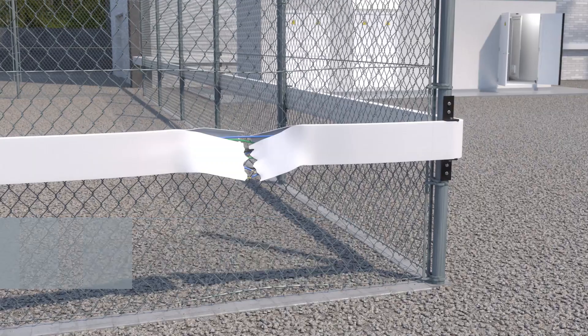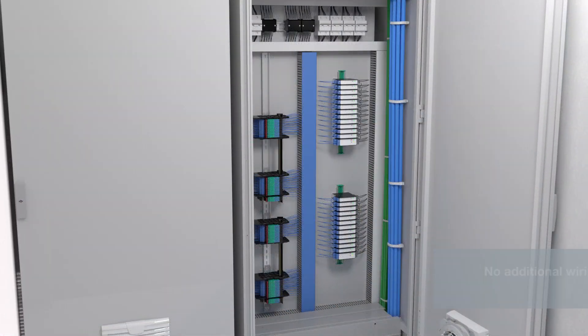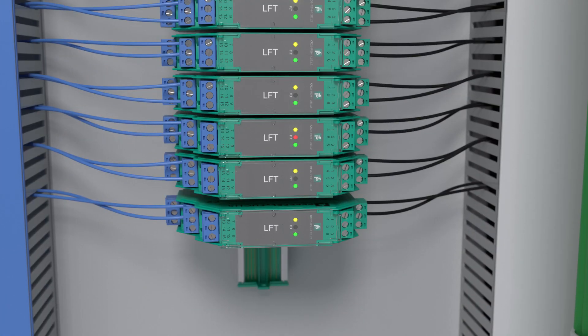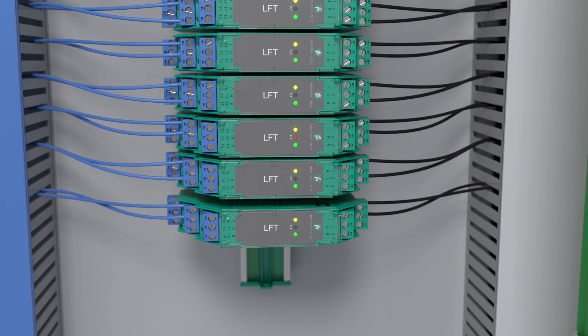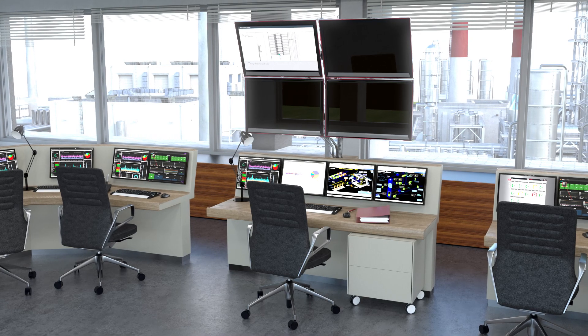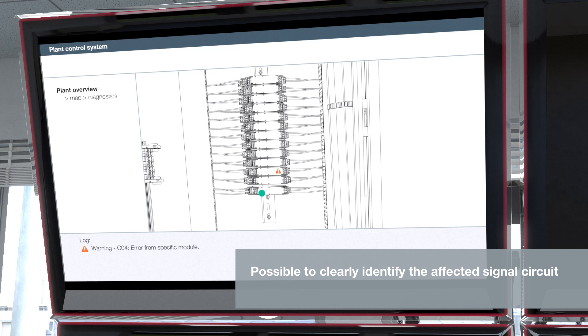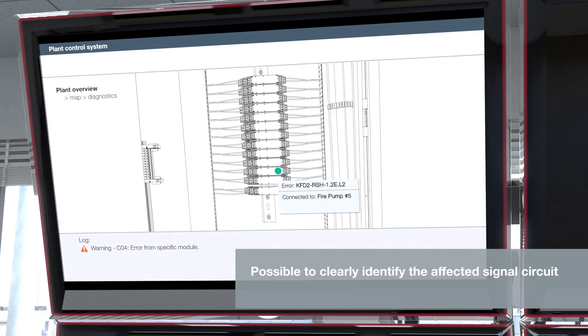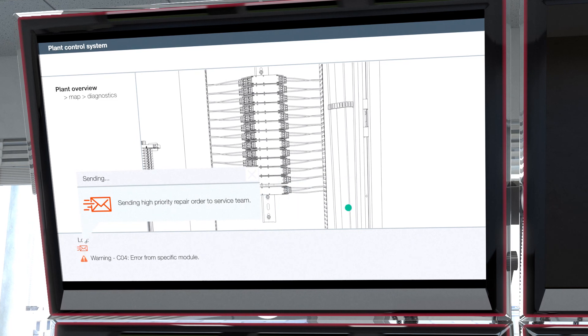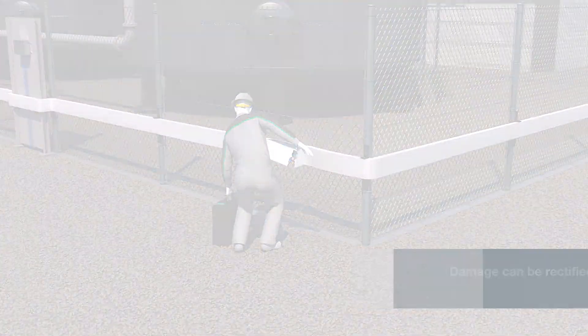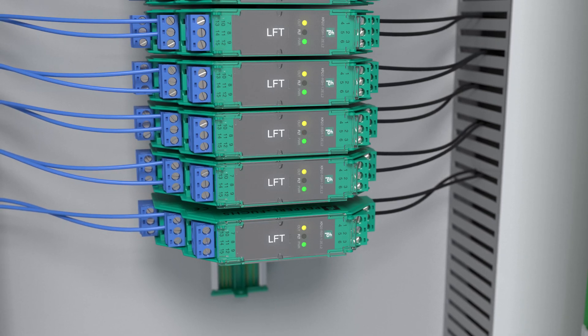Modules with line fault transparency require considerably less wiring in the field and greatly increase the level of safety. They do not only monitor switching signals — they also provide seamless monitoring of the cables on the field and control sides. Fault signals are transmitted directly from the field to the control room. Short circuits and line breakages can therefore be detected on the field side, assigned to a specific signal circuit, and directly rectified where necessary.